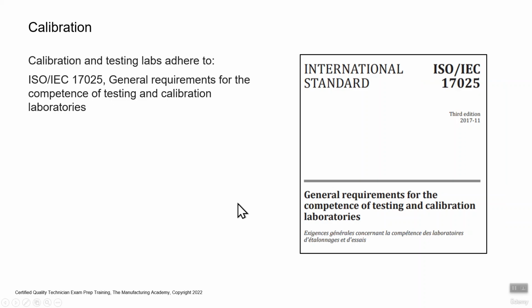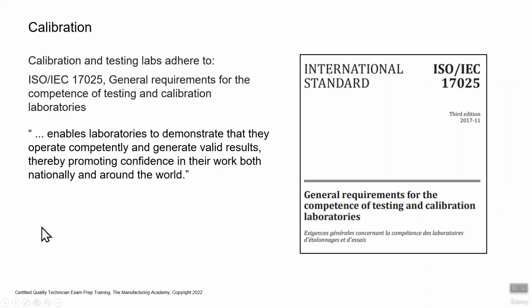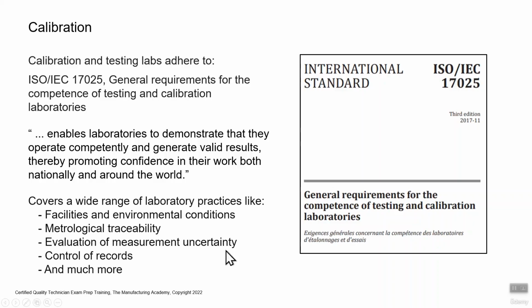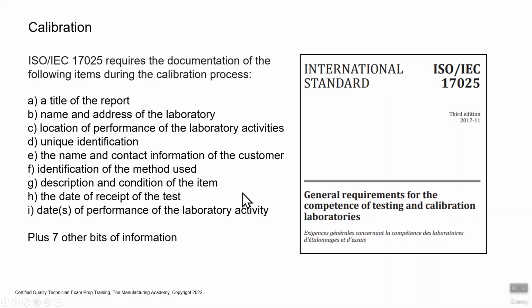So in the ISO 17025, and we talked about its purpose before, to operate competently, generate valid results. So again, this covers a wide range of practices, and one of those is the generation of a calibration certificate. So ISO 17025 requires all of this stuff. I got tired of typing, right? So the title of the report, the name and address of laboratory, the location of performance of laboratory activities, the unique identification, it goes on and on and on. All of that information is required on a certificate to fulfill the requirements of calibration per 17025.